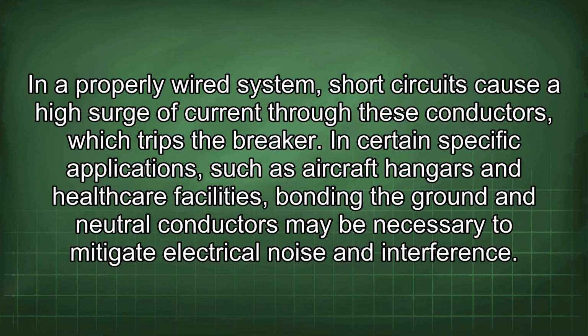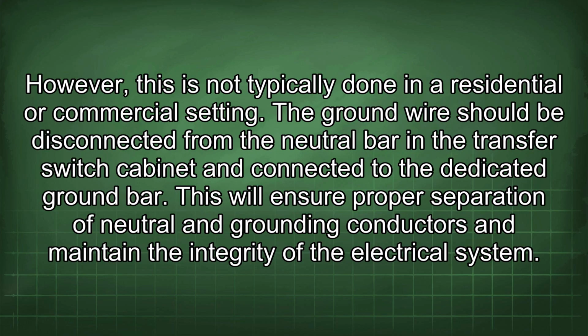In certain specific applications, such as aircraft hangars and healthcare facilities, bonding the ground and neutral conductors may be necessary to mitigate electrical noise and interference. However, this is not typically done in a residential or commercial setting. The ground wire should be disconnected from the neutral bar in the transfer switch cabinet and connected to the dedicated ground bar. This will ensure proper separation of neutral and grounding conductors and maintain the integrity of the electrical system.